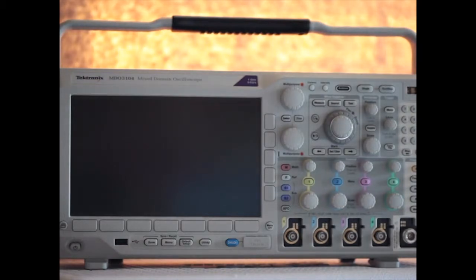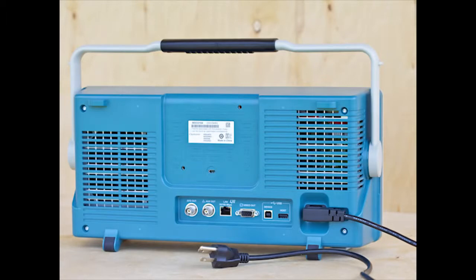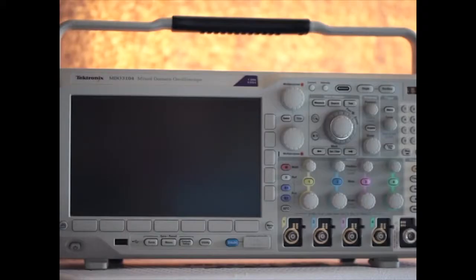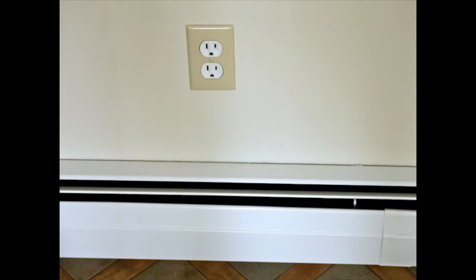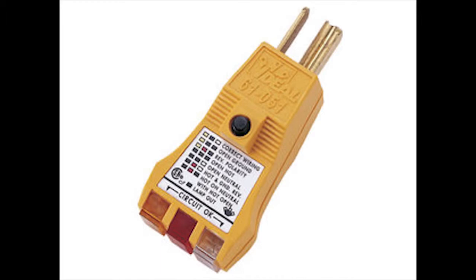It is 8 inches tall and 16.4 inches wide, with a depth of 5.8 inches. The power cord connects to the back and plugs into a standard 120-volt single-phase receptacle. The instrument is GFCI and AFCI compatible, so you don't need to worry in that regard. Just be certain that the receptacle has equipment grounding continuity back to the service entrance panel. An inexpensive circuit analyzer will verify this fact.